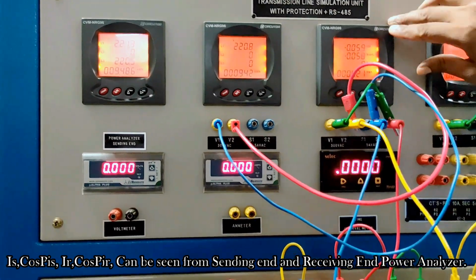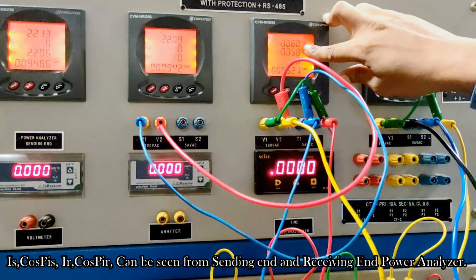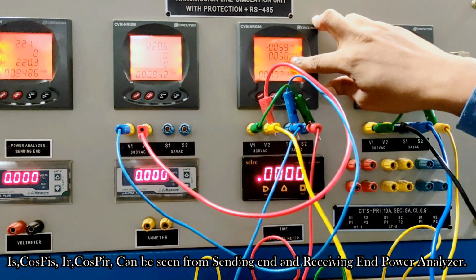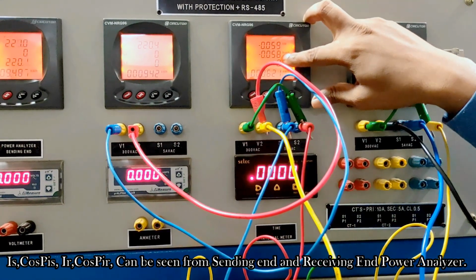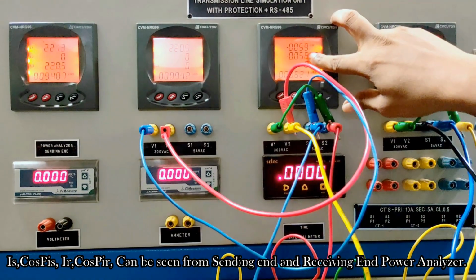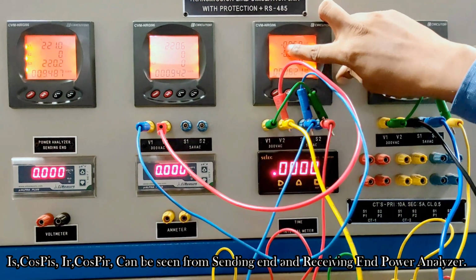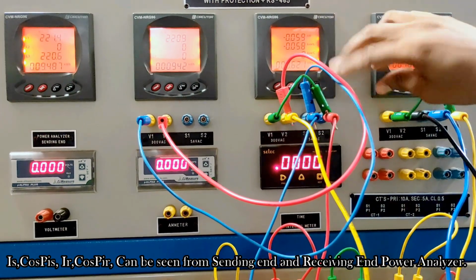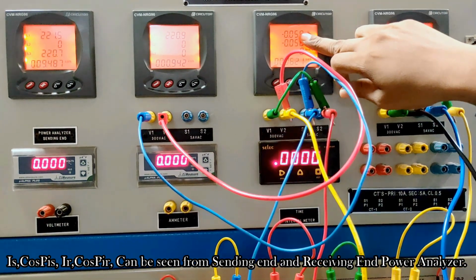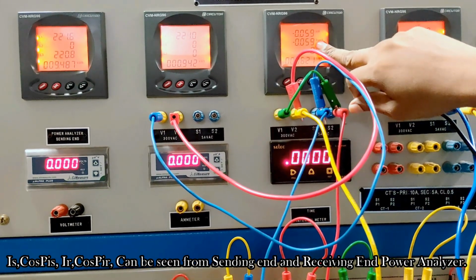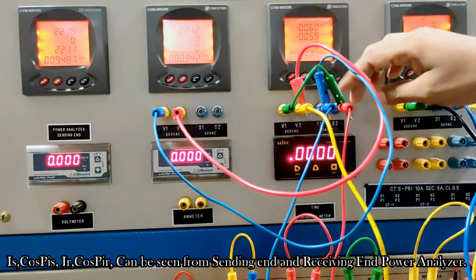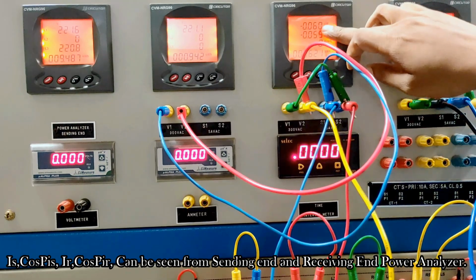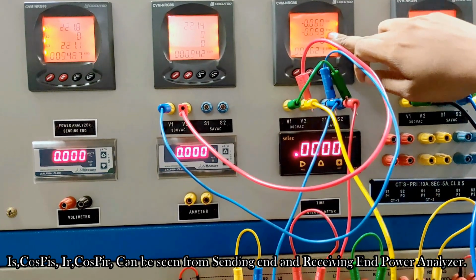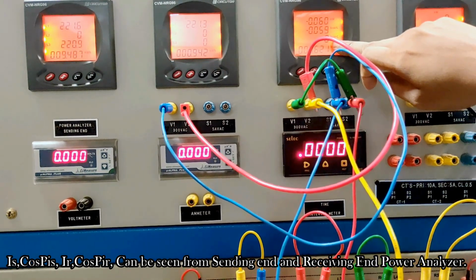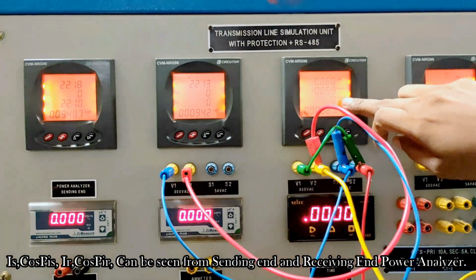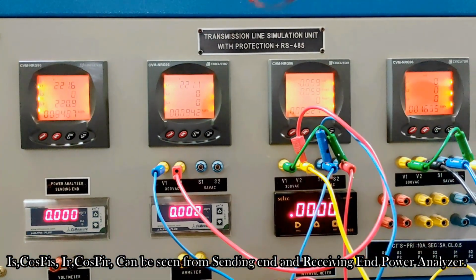And right now here you can see that this is the real power and this is the reactive power taken by the compensator. This is the PC and this is the QC, and it is showing minus, which means the connection is reversed. That's why the P is minus and the Q is also minus. If we reverse the connection, this P will be plus, this Q will be plus, but the QC of the capacitor reactive power will be minus.